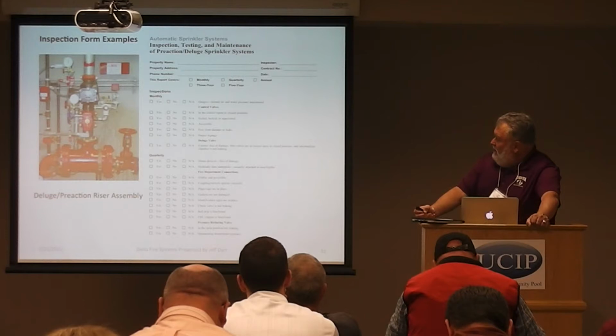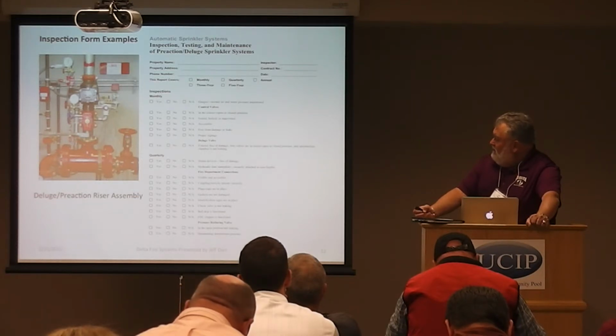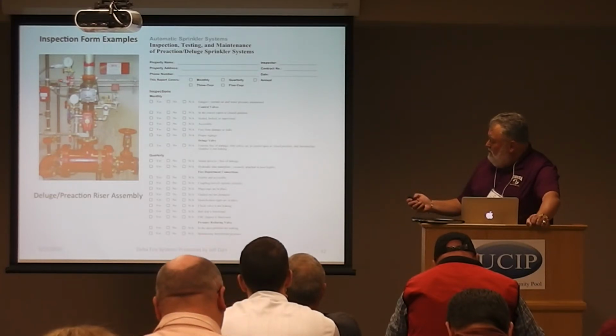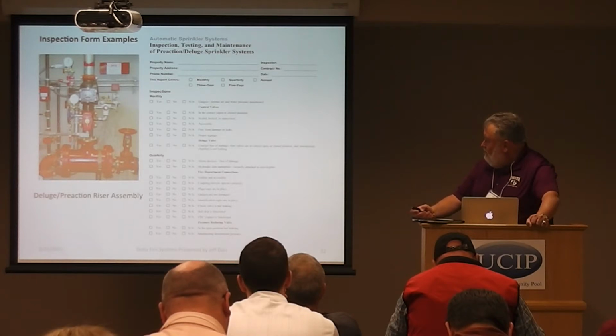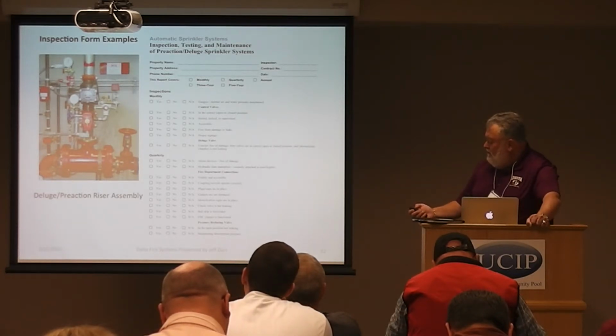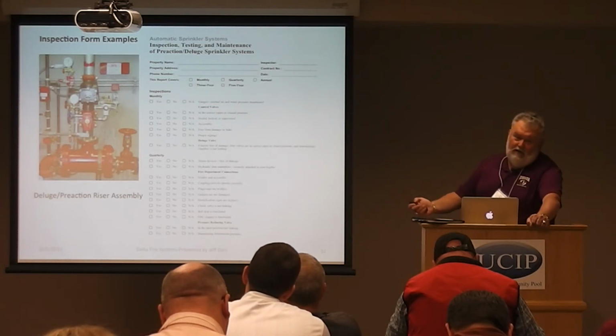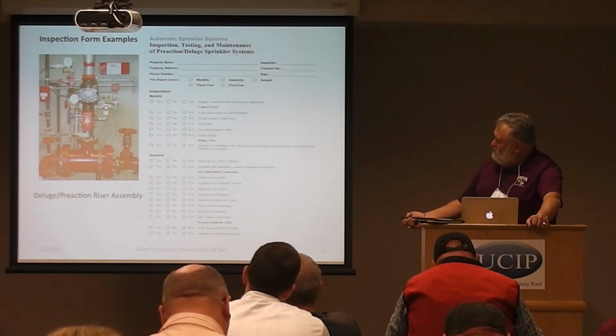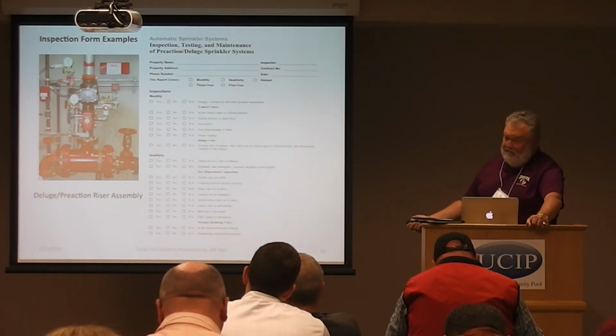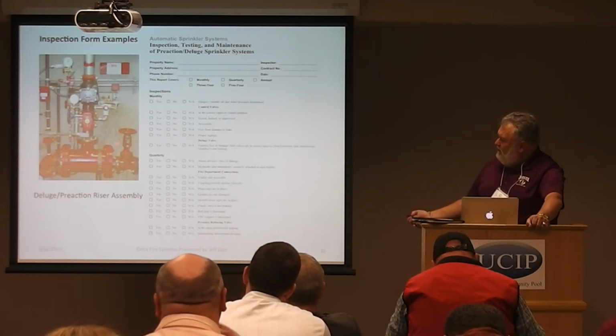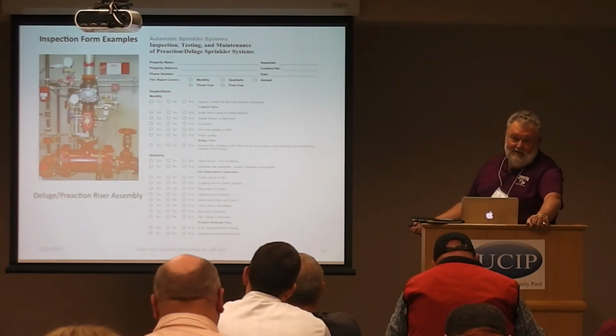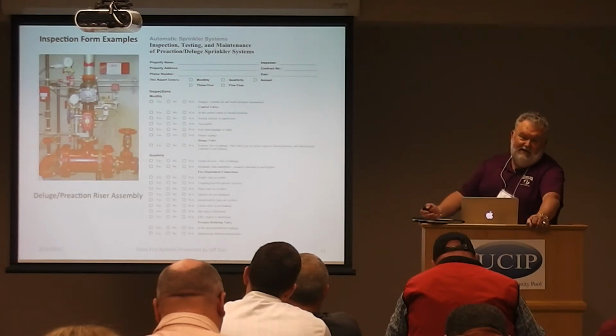Here's an example of a deluge or pre-action. Again, you can see that the valve is open on that, and the system looks to be in pretty good shape right now. It's sitting on top of a strainer. This valve here is what they call an OS&Y valve. That valve is closed, and the reason is this type of system. That's a flushing valve. This being a strainer here, it has perforations in it. This is where it picks up the debris, so every so often you have to flush that strainer out, make sure everything's out of it. That's why it's closed, because normally you don't want that operating.